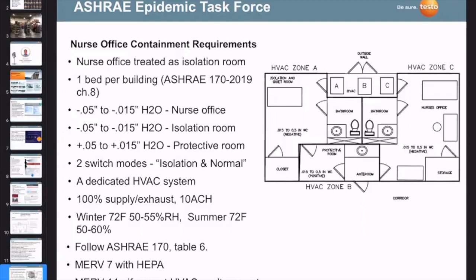But that's not all. In addition to that, we all remember the old nurse's office in our elementary and high schools and grade schools. It's a little bit different today in the sense that now ASHRAE also wants the nurse's office and her adjoining rooms, like the testing room or an isolation room, to be set up toward the ASHRAE 170 guideline, which is a clean room isolation guideline for pressurization control. The nurse's office and the isolation room to the right and to the left here need to be kept at a constant negative pressurization with respect to the corridor space, and a positive protective room should be established as a positive pressurization space, pushing airflow into the negative spaces surrounding it.